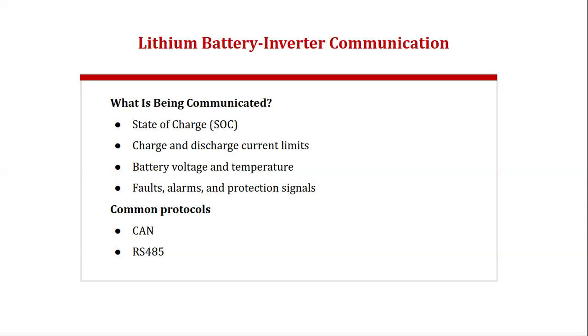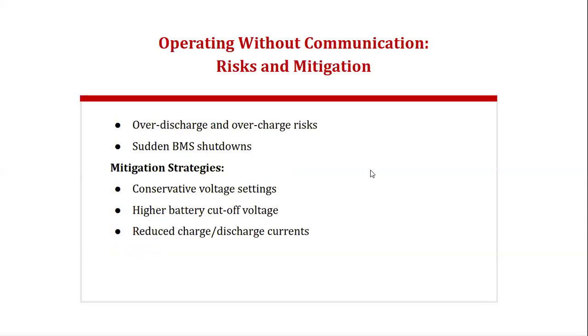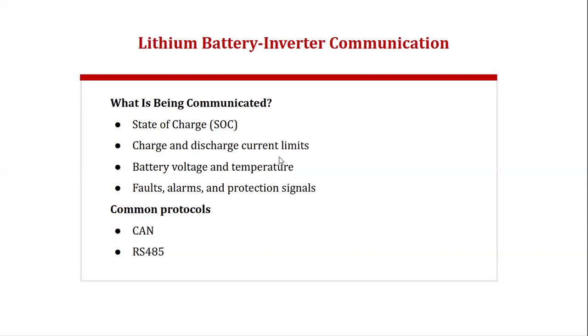So then common protocols, we have CAN and RS 485. Those are the two common protocols. Your communication cable coming from the battery, from the inverter, is either entering the one labeled CAN or the one labeled RS 485. But this is communicated to the installer in the manual. It will have been stated somewhere in both the battery's manual and the inverter manual. You will see. So you don't just take a decision that I want to connect it here. No, you must go through it and know where to connect it.